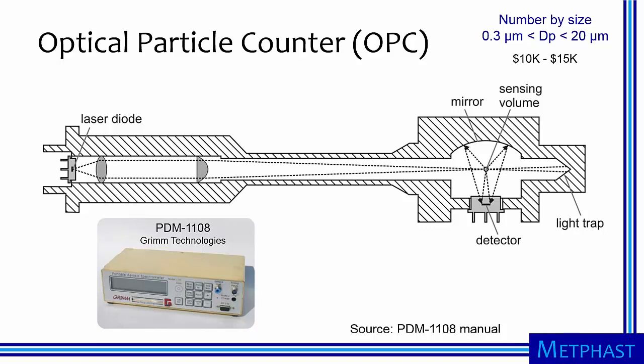The light from a laser diode is shaped with lenses to illuminate a sensing volume. A detector measures the intensity of the light scattered by each particle that enters the sensing volume. The intensity of scattered light is used to classify the particle by size, with larger particles scattering more light than smaller ones.